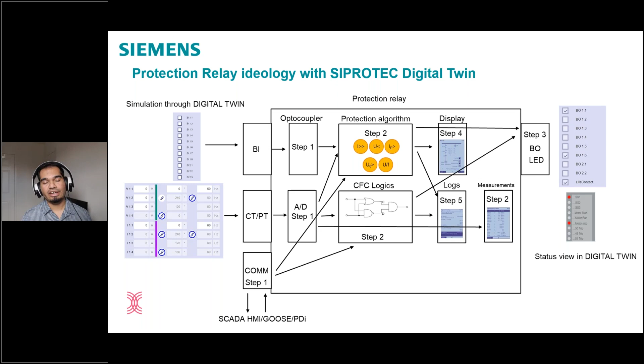On the right hand side, also we have a communication protocol. So you can also receive communication signals from either a SCADA system, or an RTU, or some simulated master. So you can use that as well. And finally, all this data is then processed in the same way like a normal physical protection relay would do it. It would process all this data and then output or export all this data on the right hand side, as you can see, via binary outputs or LEDs, or via the measurements, or via the logs, or via the display, or again through the SCADA. So that's how the ideology would look on the digital twin.